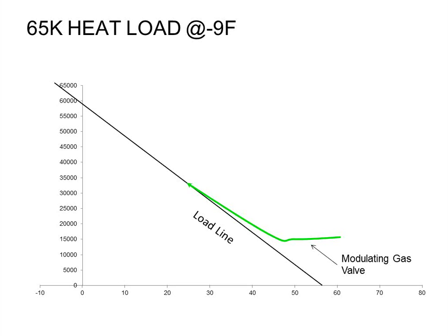And the third time that he's going to shut off is going to be whenever you go into night setback, because it's the same thing as changing your set point, basically. The thermostat automatically switched us from 72 to, say, 65 degrees. The stat told the valve to ramp down as far as it could. It couldn't ramp down any further, so it basically said, well, I better stage off for a while and let the temperature in the house drift down to 65, and then I can go ahead and re-enable myself after that. So when it's fairly mild outside, when I change the set point manually, or when I go into nighttime setback or any time of unoccupied setback, those are the times the gas valve actually could shut off.